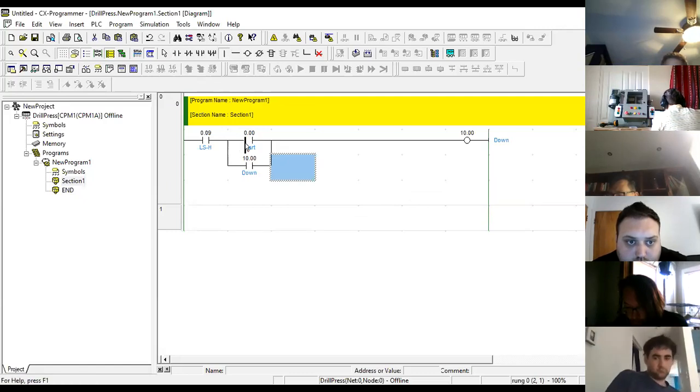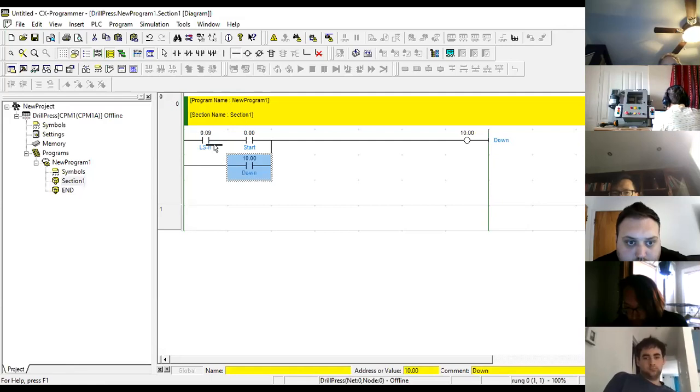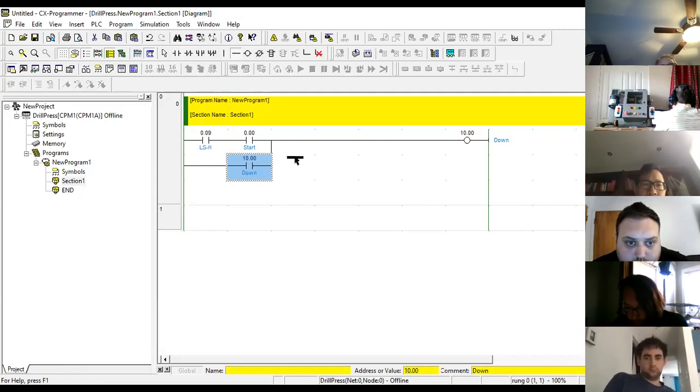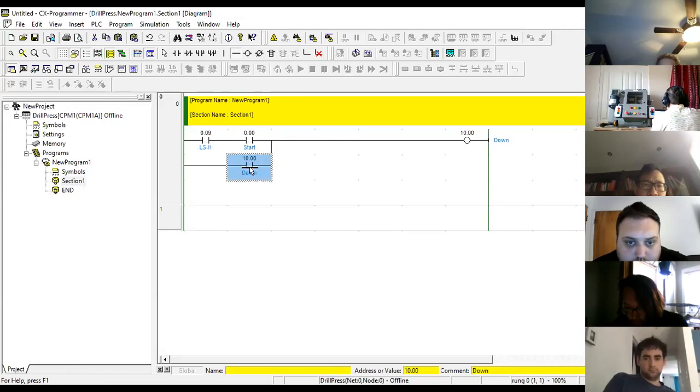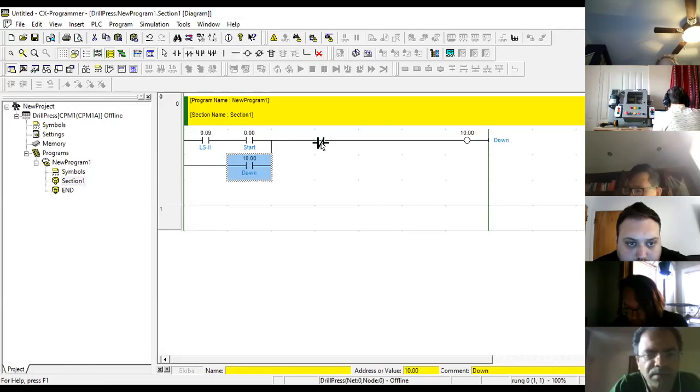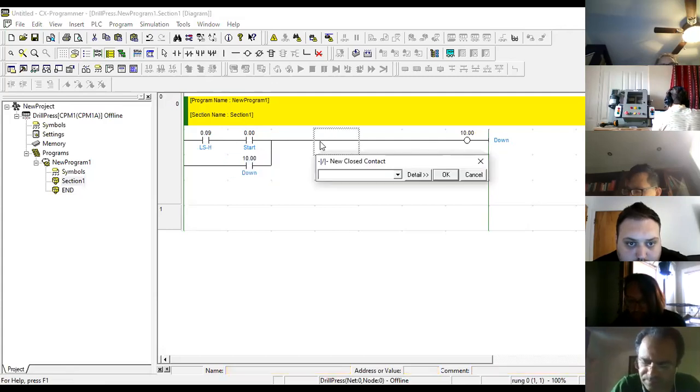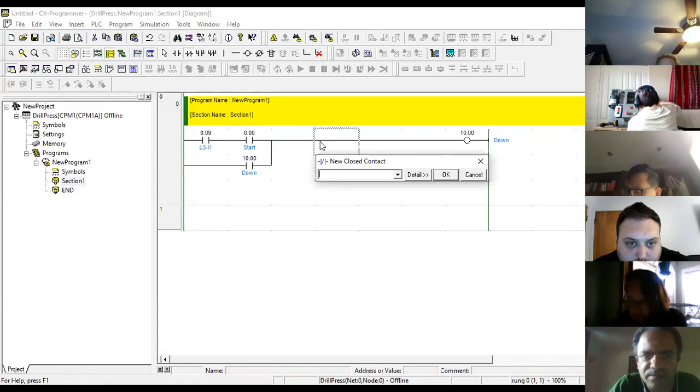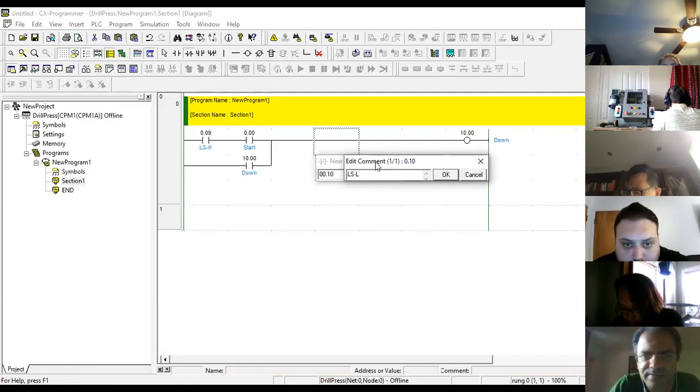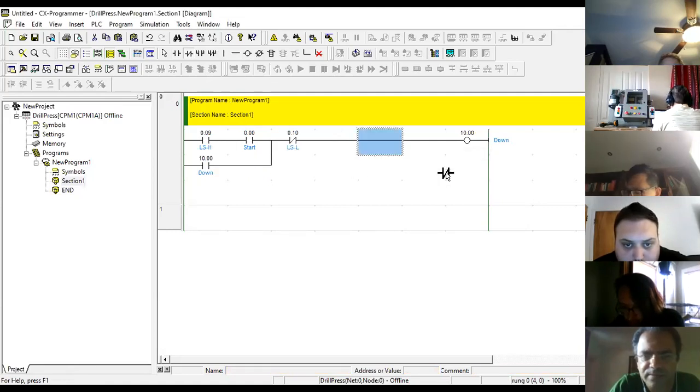But we know that we can't maintain this way here. We have to maintain both because when it starts going down, I'm going to lose this limit switch here. You always have to think in order. So now I know that if I hit the limit switch and start, I'm going to start going down. But when am I going to stop going down? I have to put something that will actually stop it from going down, which is going to be my limit switch low. And if I activate my input here on PLC, it's 10.00, so 00.10. And this is my limit switch low. That's my first network.